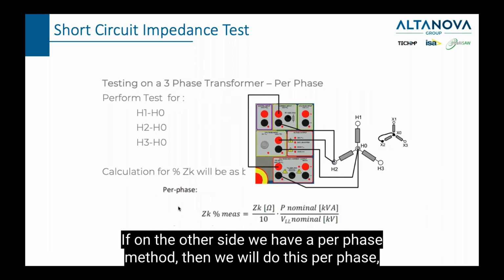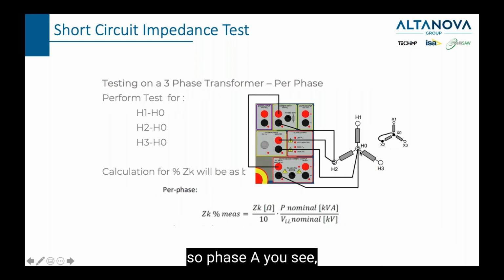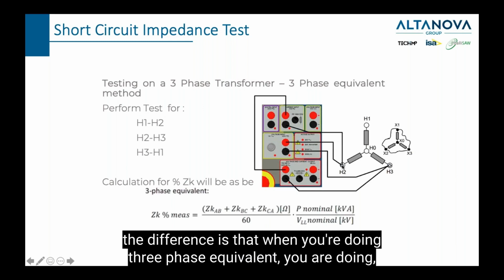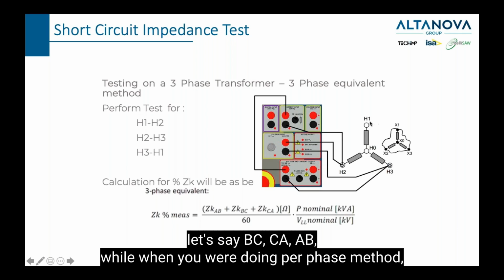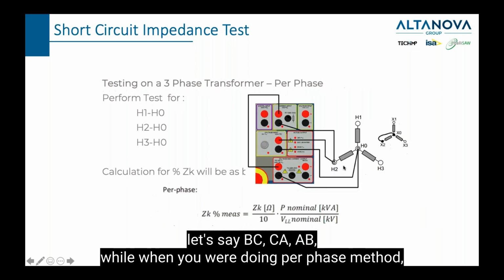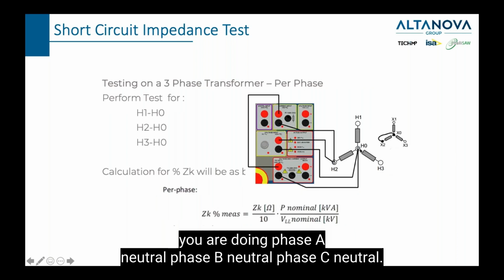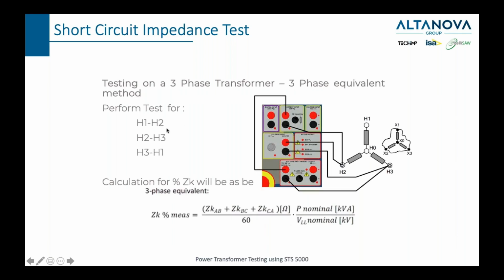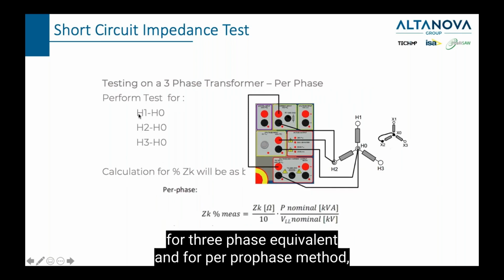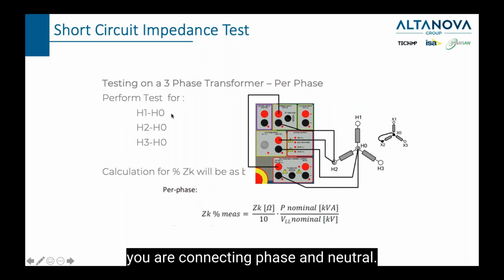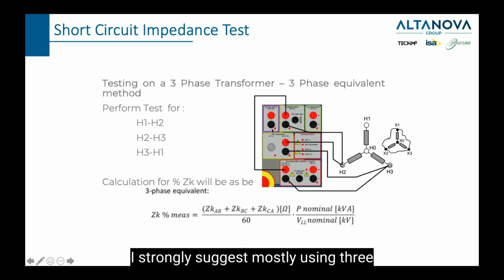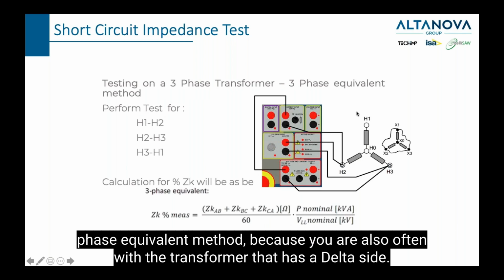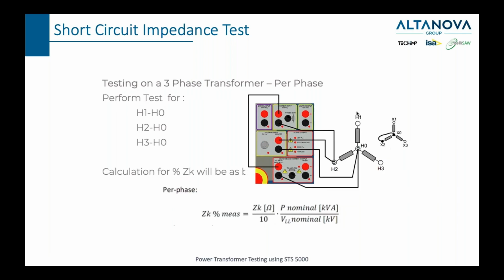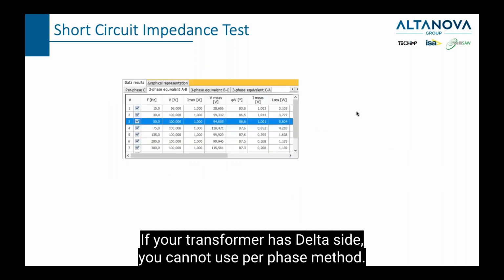If, on the other side, we have a per phase method, then we will do this per phase. The difference is that when you're doing three-phase equivalent, you're doing, let's say, BC, CA, AB, while when you're doing the per phase method, you're doing phase A, neutral, phase B, neutral, phase C, neutral. So you see, here you're connecting between phases for the three-phase equivalent, and for the per phase method, you are connecting phase and neutral. I strongly suggest mostly using the three-phase equivalent method because you often deal with a transformer that has a delta side. If your transformer has a delta side, you cannot use the per phase method.